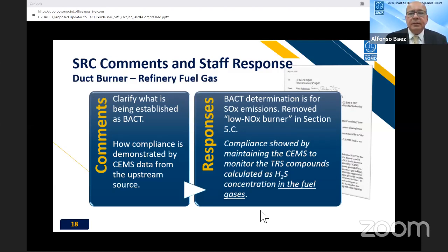Go ahead, Dipankar. Okay, you can hear me, right? What I'm saying is, it is not actually an emissions monitoring system, but what this system does, as Bahare was pointing out, is continuously measure, maybe every 10 or 15 minutes, using a gas chromatograph and a sulfur chemiluminescent detector, the TRS or sulfur content in the refinery gas. Now, in some cases, if the limit under Reclaim or Rule 218 is, say, an SO2 emissions limit, the computer system takes the total sulfur and converts it into SO2 emissions. So the total sulfur monitor is in a way part of the CEM, but it's also correct that the TRS system is not directly measuring emissions—it leads toward determining SO2 emissions in terms of pounds per hour, mass emissions like that.